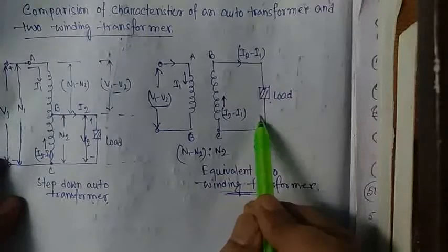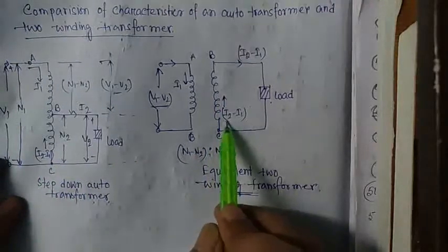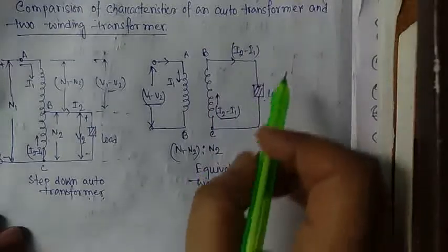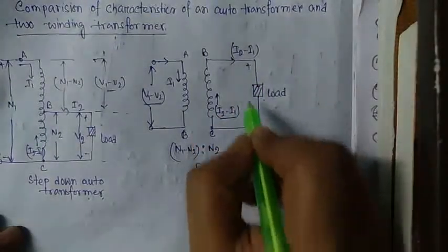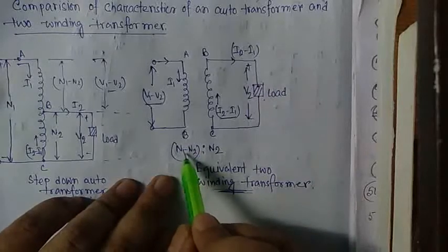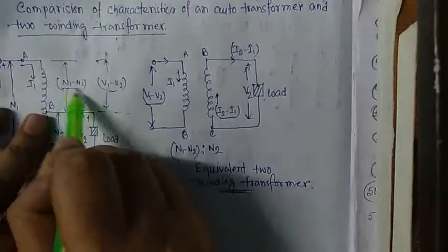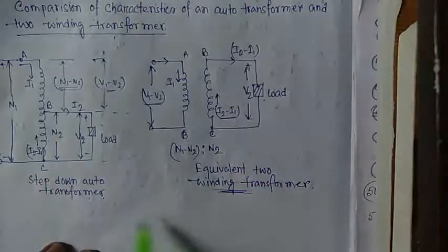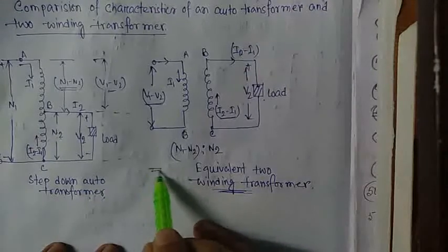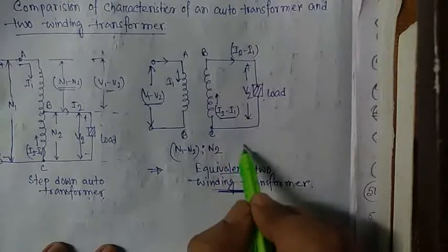In the secondary side the current flow is I2 minus I1, and the voltage across the load is V2. The turn ratio is N1 minus N2 to N2. So this step down autotransformer can be drawn as an equivalent two winding transformer, as shown in figure number 2.